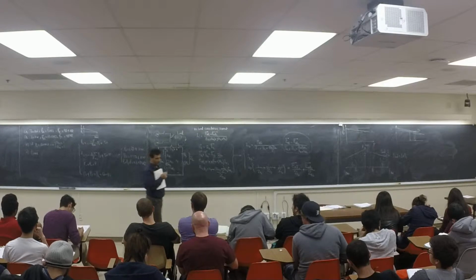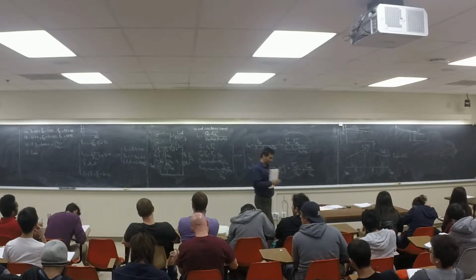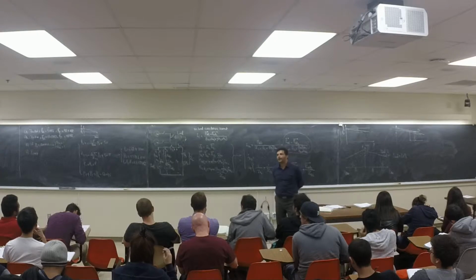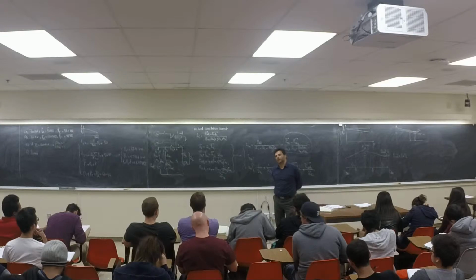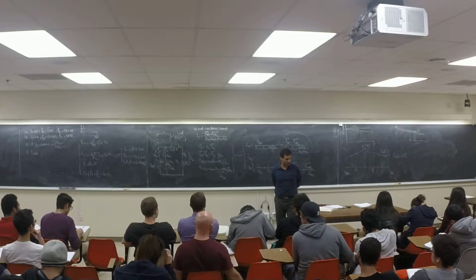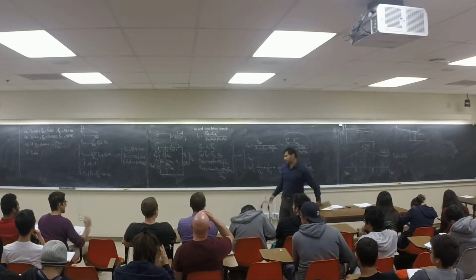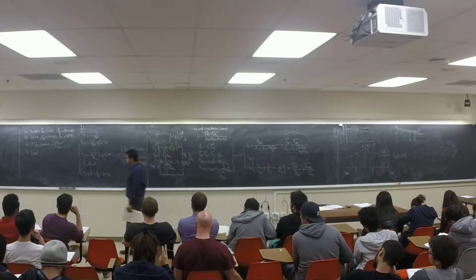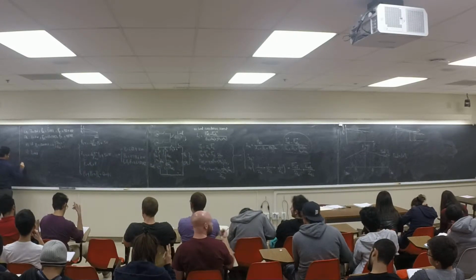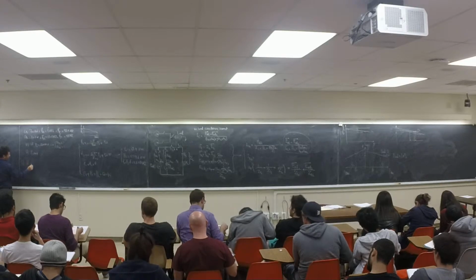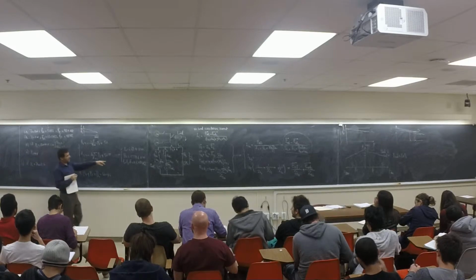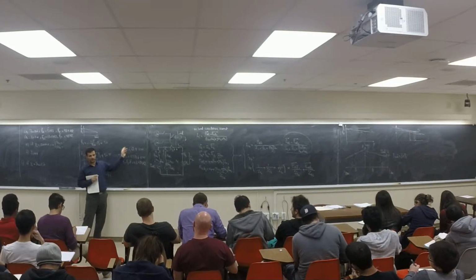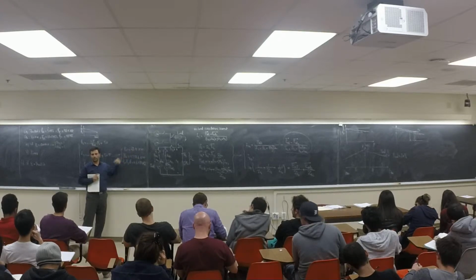Now you tell me how to solve the B part. Set the frequency at 48.5. Set P1 to max, 700, or F1 equals 500. Why are you setting P1 to max? Because P1 is the one who's going to hit the max first, right? Just based on what I'm seeing here, the one that is going to hit the 700 kilowatt first is going to be this one, right? So let's set P1 to 700 kilowatt.